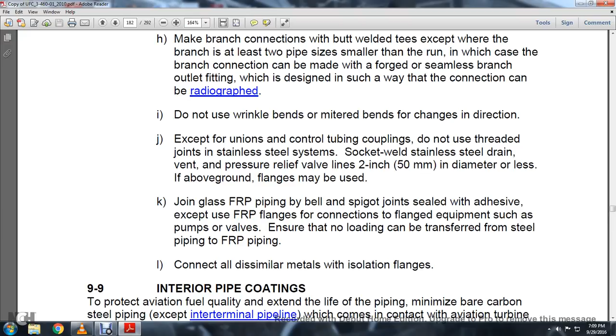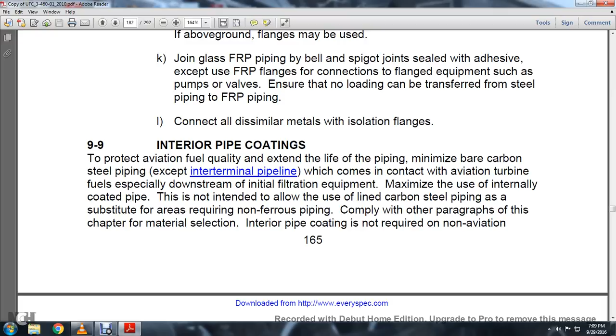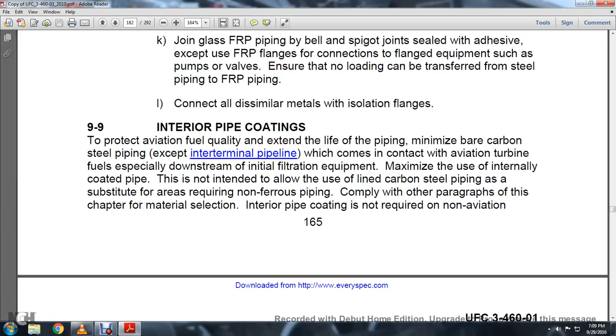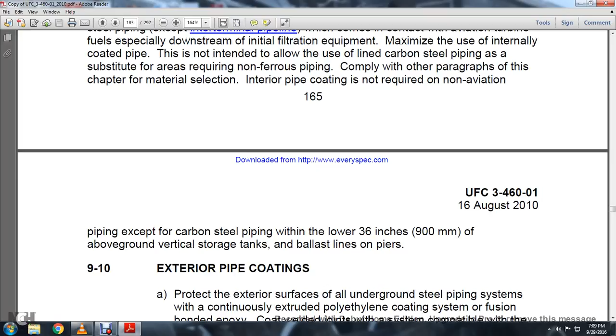9.9 Interior pipe coatings. To protect the aviation fuel quality and extend the life of the piping, minimize bare carbon steel piping, except for the interterminal pipeline which comes into contact with the aviation turbine fuel, especially downstream of initial filtration equipment. Maximize the use of internally coated pipe. This is not intended to allow the use of lined carbon steel piping as a substitute in the areas required for non-ferrous piping. Apply the other paragraphs of the chapter on material selection. Interior piping coating is not required for non-aviation piping, except for carbon steel piping in the lower 36 inches of the above ground vertical storage tank and ballast lines on piers.